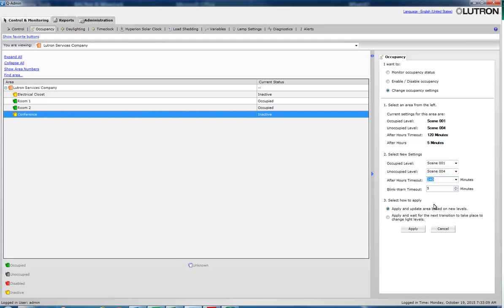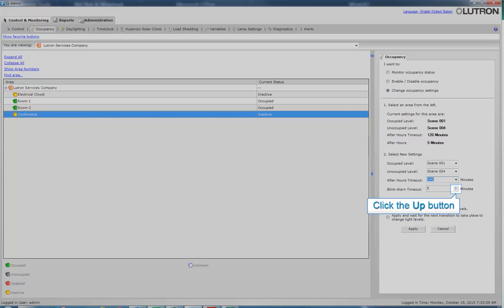Now, let's change the blink-warn timeout to 10 minutes. The blink-warn timeout is the amount of time the user will have after the lights flash to manually override the system.